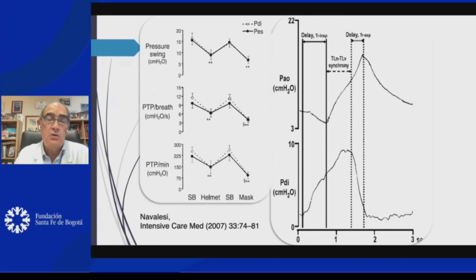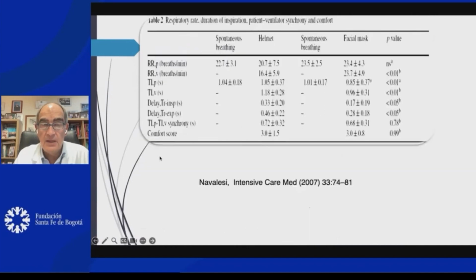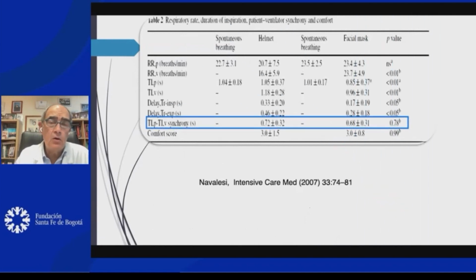However, if you compare to the use of a facial mask, both interfaces are capable of reducing the pressure swing, looking at the esophageal pressure, reducing the work of breathing, depicted as PTP per breath or PTP per minute. Interestingly, if we compare the duration of the assistance to the diaphragm, you can see the time during which there is synchrony with the two devices. You can immediately realize that the times during which the diaphragm is really assisted are very comparable. Then we can conclude that probably, especially by using the helmet, there is no major issue if dyssynchrony occurs.